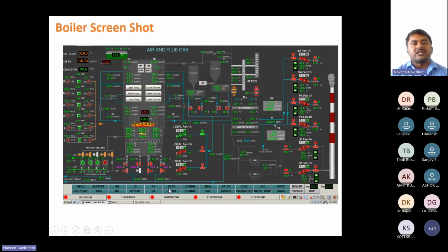So this is the practical screenshot. This is the boiler. This is the coal handling, coal feeders. The coal which is coming from the coal bunker, after crushing in the crusher, comes down to here. So these are the fans. There are two SA fans and two PA fans. ID fan is for extracting the flue gas. So these are supplying air to the boiler through APH, air preheat heat exchangers.